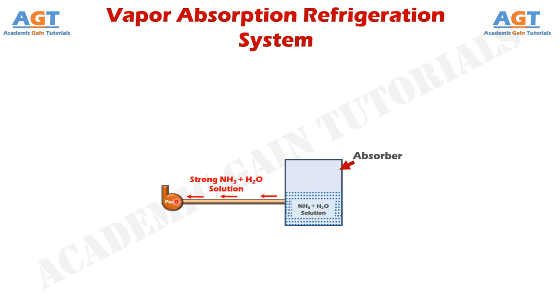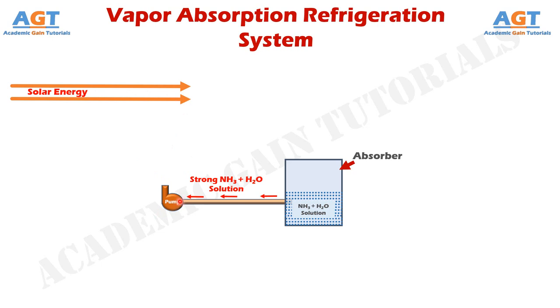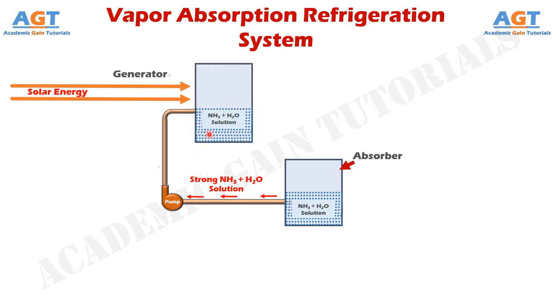First of all, here we have an absorber. Inside this absorber, we have a solution of ammonia and water. And beside this absorber, there is a pump. Now, when solar energy is supplied to the system and the generator, then this pump starts working. Using this pump, we will pump this solution of ammonia and water from the absorber to the generator. So, the function of this pump is to transfer the solution from the absorber to the generator, which is running on solar power.